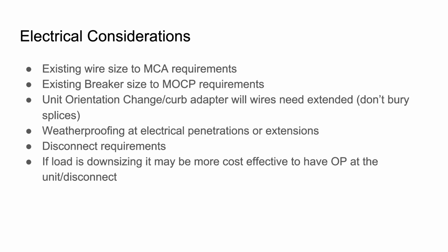Electrical considerations. This is mostly to do when you're replacing a unit, but I guess it is all the time, even if you're putting in new. If you're doing new, presumably somebody has done some of these calculations for you and there's some engineering there to follow. But if you're replacing a unit, a lot of times there's a lot of options that you can select to replace this unit. And if you're changing it to something that requires a change in wire size, especially if it's a really long run, that expense change is a huge change. If you're landing on a breaker panel that has big square body breakers, that could be a $2,000-$3,000 breaker. So considering that when you're going in, if you can directly match it, that's sort of ideal.